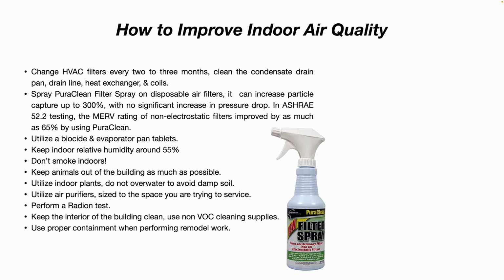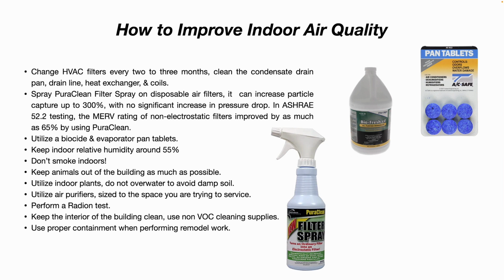So as we move down the list here, utilize a biocide and evaporator pan tablets. When you clean out your evaporator pan, if it had standing, dirty, nasty water, you can use a biocide, especially if there was mold growth in that pan. Then you drop in these pan tablets after you've cleaned the pan, and it'll help keep it clean over the long run, help reduce odors, help reduce water damage. They can be used not only in AC condensate drain pans, but in dehumidifiers, humidifiers, refrigerators, etc. You can buy those just about anywhere, different manufacturers, different price ranges. That little pack there you see on the screen was right around $6.